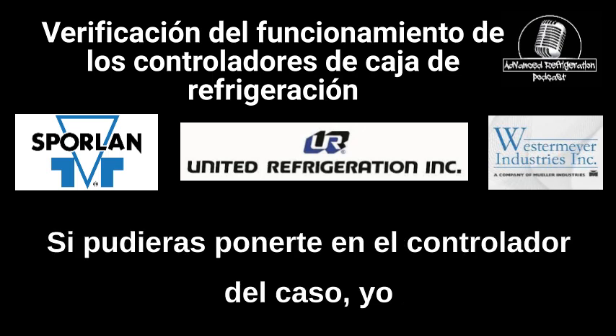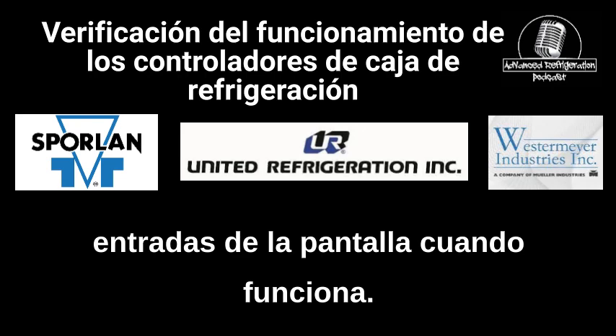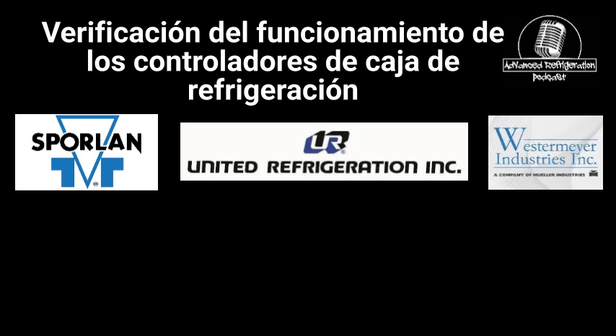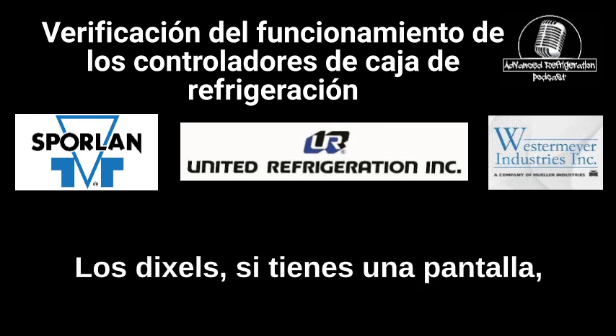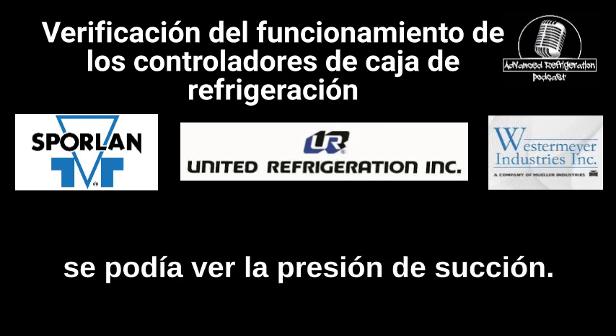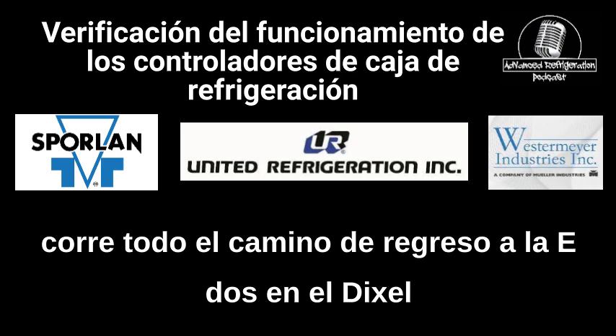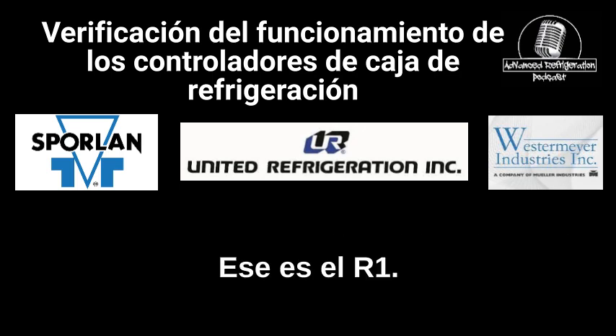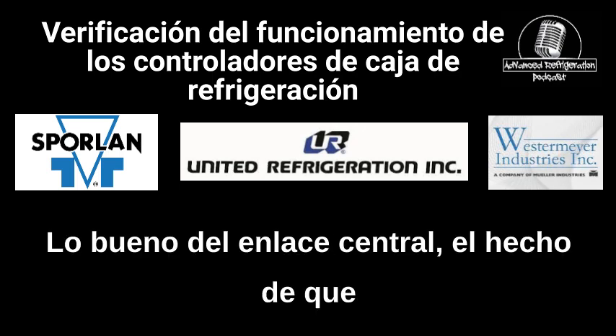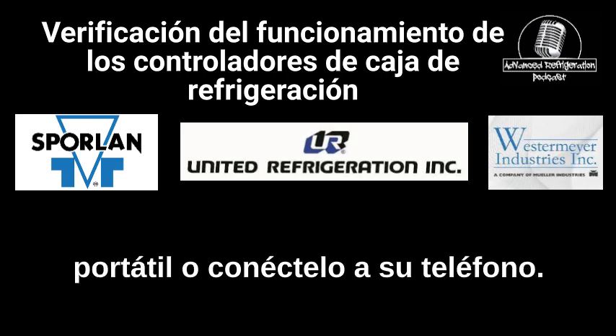So as you're doing that, if you could get on the case controller, like I know on the CoreLinks, you could see certain inputs from the display when it works. If you could see those, that's great. The Dixels, if you have a display, you could see the suction pressure. So if you need to track it, instead of running all the way back to the E2, on the Dixel stuff, if you have the display there, you could check it. That's the one real nice thing about CoreLink, the fact that you can either hook it right up to your laptop or hook it up to your phone.